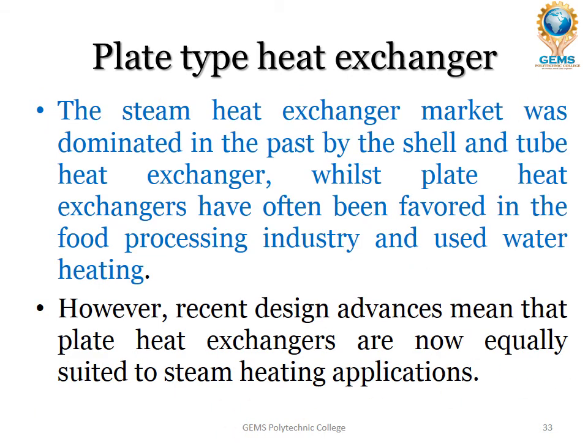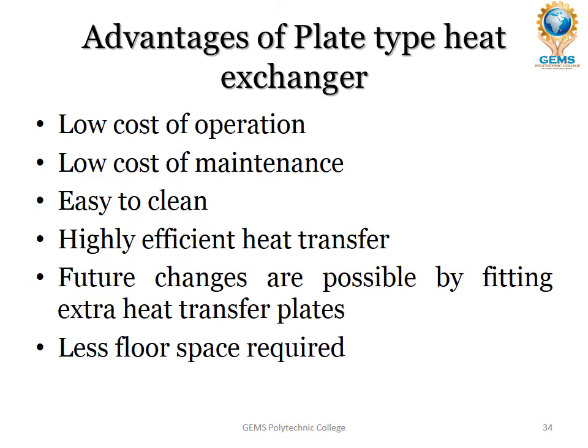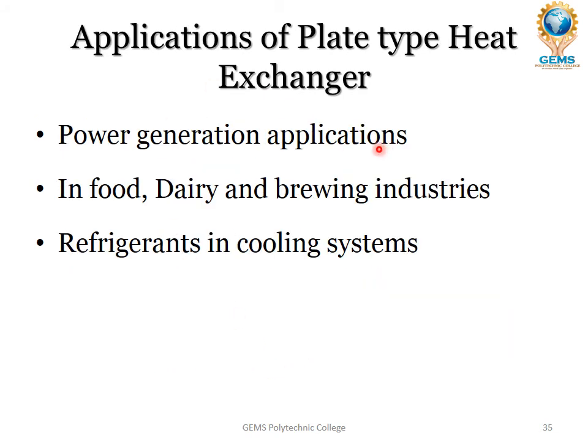The steam heat exchanger market was dominated in the past by the shell and tube heat exchanger, whilst plate heat exchangers have often been favored in the food processing industry and used for water heating. However, recent design advances mean that plate heat exchangers are now equally suited to steam heating applications. So, advantages of plate type heat exchangers: low cost of operation, low cost of maintenance, easy to clean, highly efficient heat transfer. Future changes are possible by fitting extra heat transfer plates, less floor space required. Applications: power generation, food, dairy, and brewing industries, refrigerants in cooling systems.